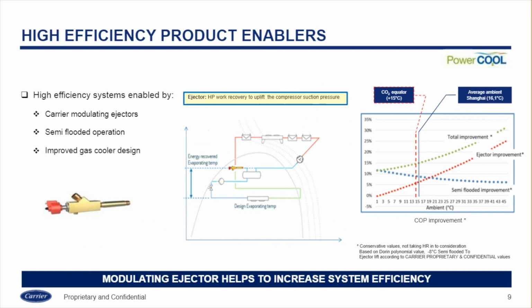Being a high efficient product for CO2 transcritical, we have two major enablers to make sure it is highly efficient. The first one is Carrier's patented modulating vapor ejector. This is what we use to increase the system performance by uplifting the compressor suction pressure. We use the high pressure gas from the gas cooler, in other words the condenser, to uplift the suction gas for the compressor. In that scenario, the inlet suction pressure of the compressor can be uplifted about 3 to 6 bar, which reduces the compressor power input. So this is very simple logic.